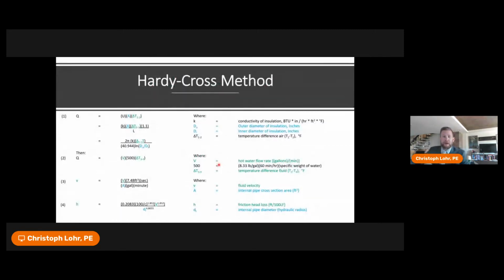All right, so when we talk about the methodology, and that's what I'm going to focus the bulk of my presentation on here. In essence, we have 4 equations. So you can see here the 4 equations. One is dealing with the assumption of conduction, heat transfer from the pipe through the insulation to the ambient air. The other one is the heat transfer of the fluid as it flows. Equation 3 is for velocity, determining the velocity. And the 4th equation is head loss. Again, in order to properly size a pump, there's 2 criteria we need to know: the flow rate and the head. Now, when we're designing hot water return systems, we are assuming a steady state condition.